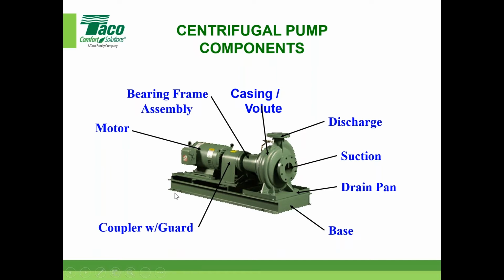You know, and ours is a welded 4-channel base. There's other ones out there. I know that the TACO bases are designed to the Hydraulic Institute standard. The Hydraulic Institute is a group of pump manufacturers worldwide that have put standards together to make sure we meet minimum requirements. And this is for all pumps, industrial and whatnot, pressure PD pumps, as well as these basic HVAC pumps. Ours does have a drain pan right here.